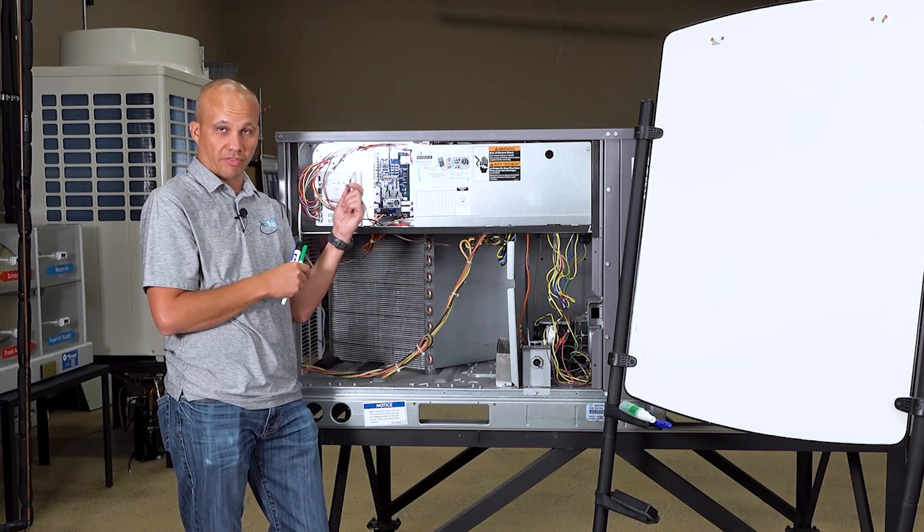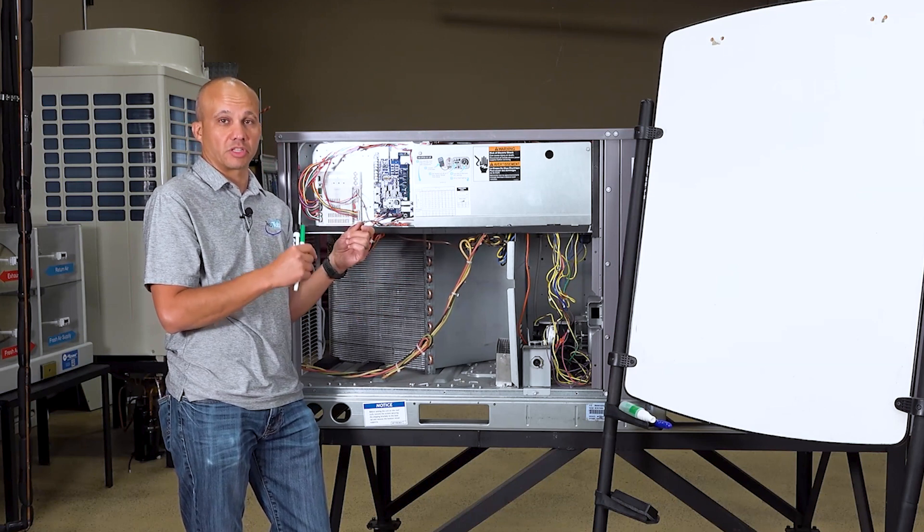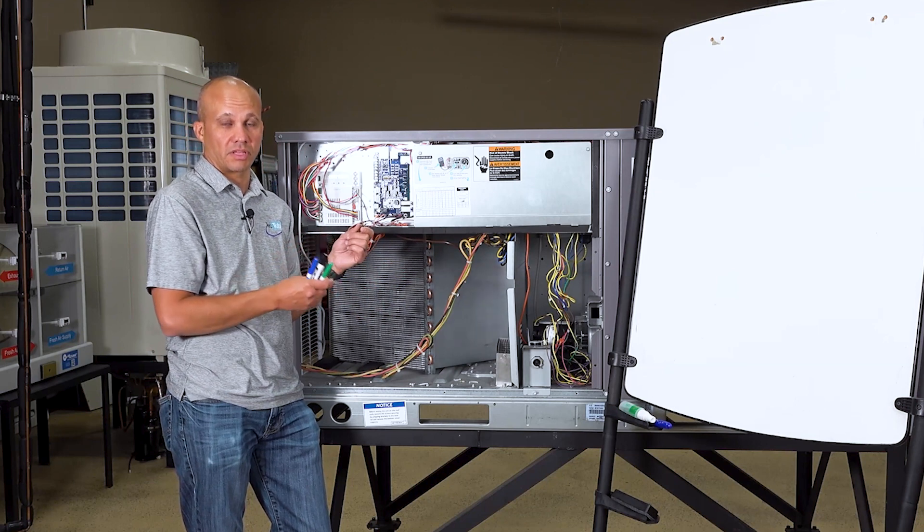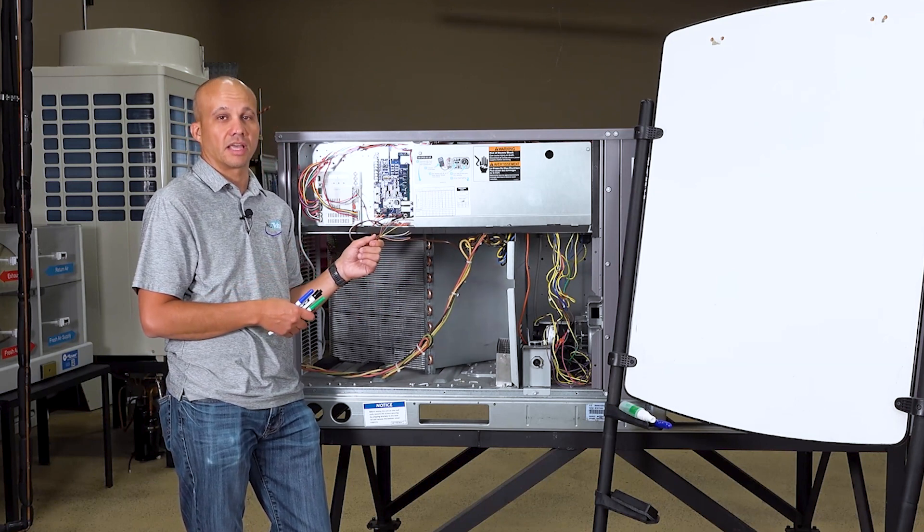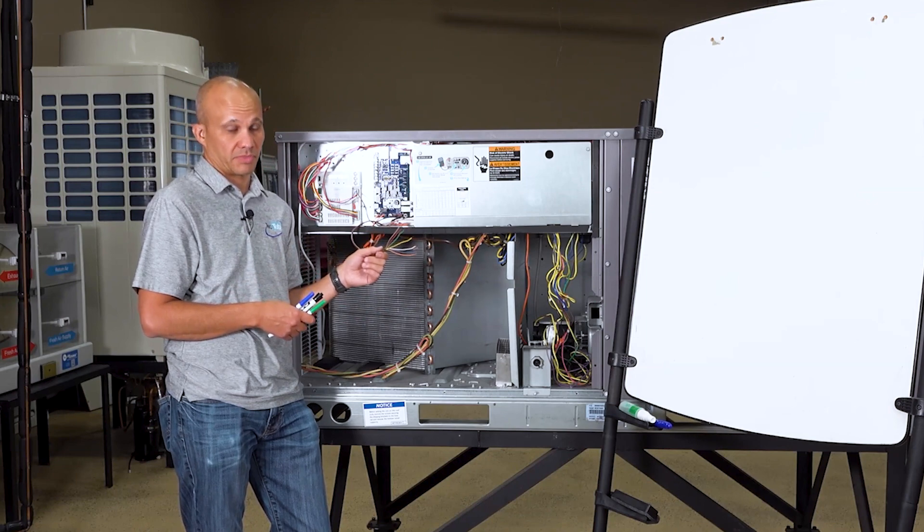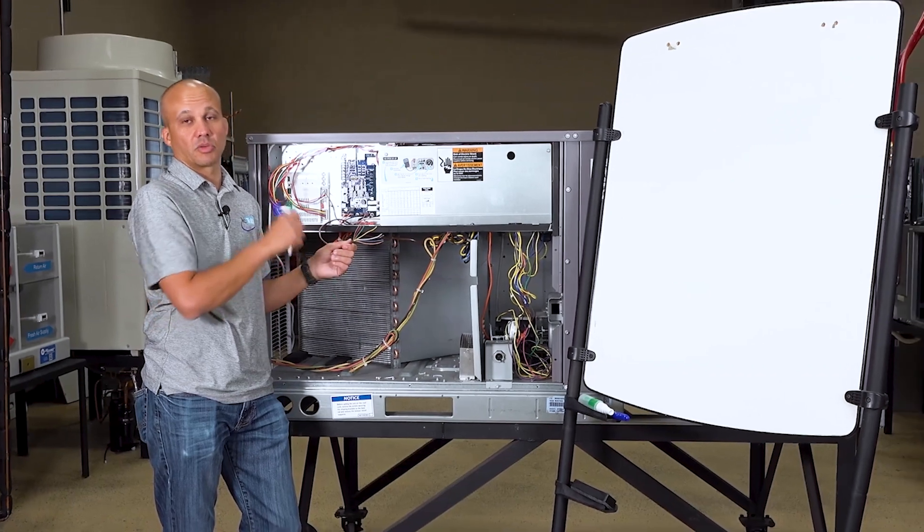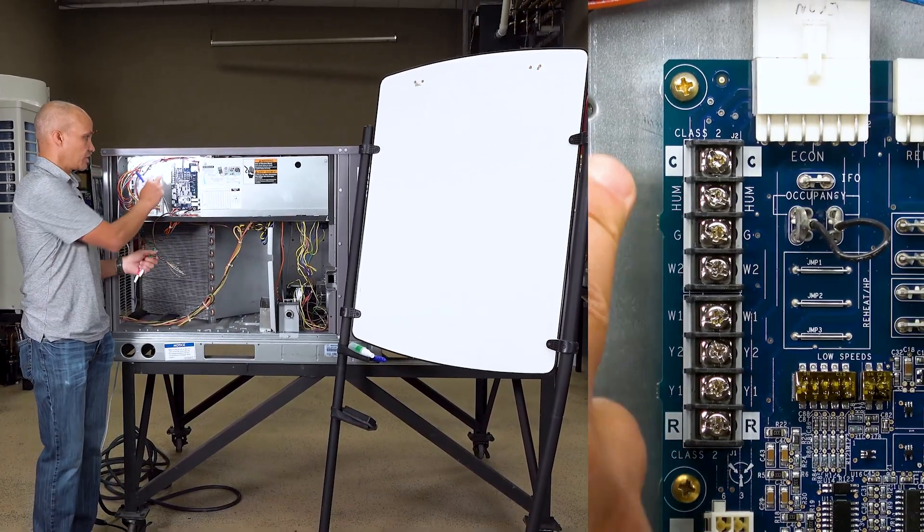Each of these wires coming from our thermostat downstairs has a specific responsibility and job. Generally speaking, they follow a standardized color coding system, although because of the availability of wires that someone has on a project, it may not always be this color system. So you're essentially matching whatever it says here, such as G, to what it says downstairs on the thermostat also labeled G.